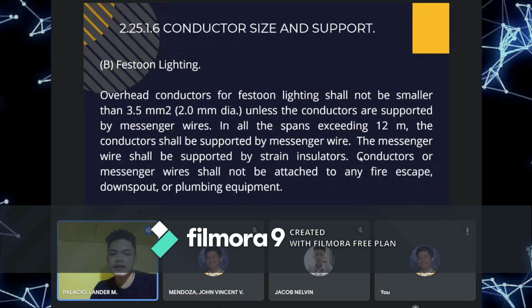So for the festoon lighting, yung mga overhead conductors shall not be smaller than 3.5 square millimeters or may diameter na 2.0 millimeters, unless the conductors are supported by messenger wires. So in all spans exceeding 12 meters, the conductor shall be supported by messenger wire. The messenger wire shall be supported by strain insulators. Conductors or messenger wire shall not be attached to any fire escape, downspout, or plumbing equipment. So dito sa festoon lighting, it should be supported daw siya ng messenger wire. And yung messenger wire should not be attached or naka-install sa mga fire escape, downspout, or plumbing equipment.